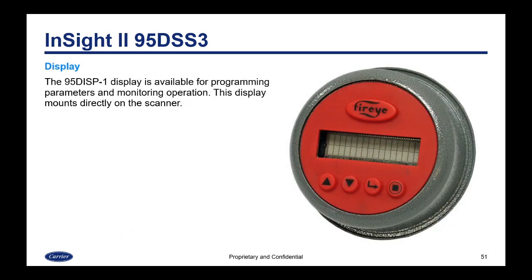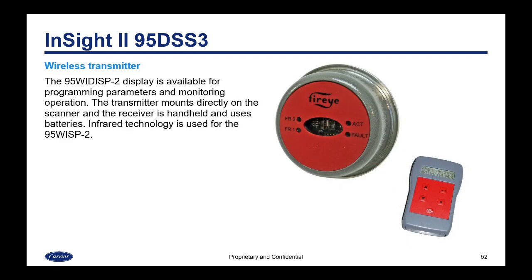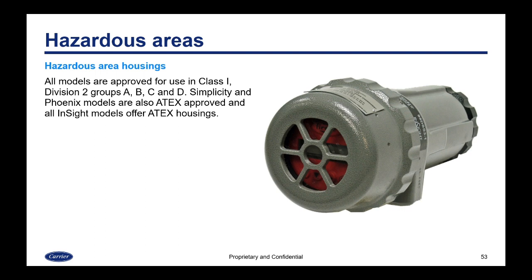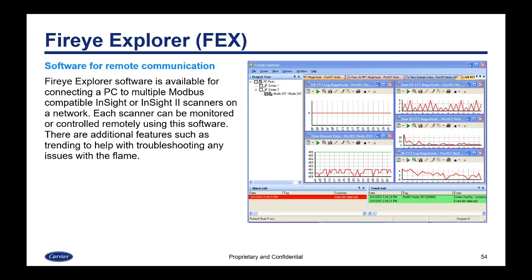The InSight 2 display is available to mount directly onto the scanner. There's also a wireless transmitter option — you put the transmitter on the scanner and use the handheld receiver to program settings or monitor operation. For hazardous areas, an ATEX-approved housing is available for all InSight scanners, as well as for the Simplicity and Phoenix. Fireye also offers Explorer software for remote communication, available for connecting a PC to multiple Modbus-compatible InSight or InSight 2 scanners on the network. Each scanner can be monitored or controlled remotely, and there are additional features such as trending to help troubleshoot any flame issues.